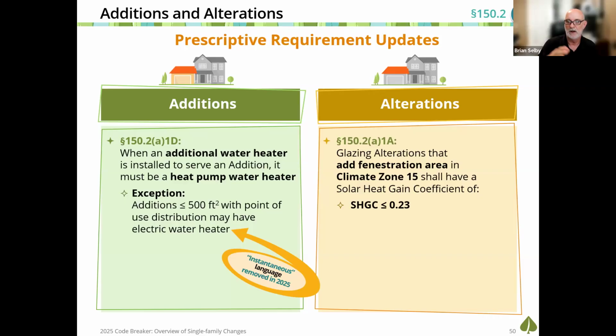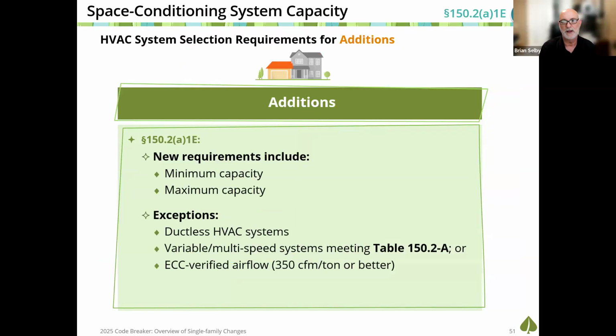Likewise, going over to alterations, glazing alterations that add fenestration area in climate zone 15. This is kind of trivial. Again, climate zone 15 reduced the solar heat gain coefficient requirements to 0.20. Means if you're doing that as part of an alteration, you can still use the 0.23 value prescriptively and comply. Space conditioning system capacity, again, prescriptively required for additions. There are new requirements for minimum capacity and maximum capacity. So we're not going to get into the details about that, but there are some exceptions.